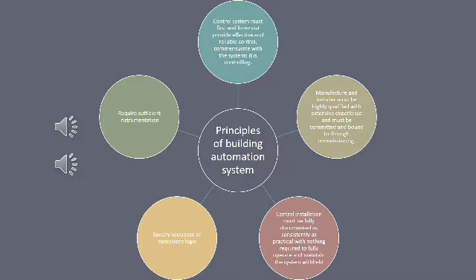The ultimate quality of the control system is primarily determined by the components installed in the building, such as those that execute logic, actuate, and document the system for maintenance of the building controls. Manufacturers and installers must be highly qualified with extensive experience and must be committed and bound through commissioning. The control system's power and quality is very important. That's why the expertise and commitment of the installing contractor, and the contractor's collaboration with the overall commissioning team, is needed in order to get a better quality product suitable for the building design and purpose.